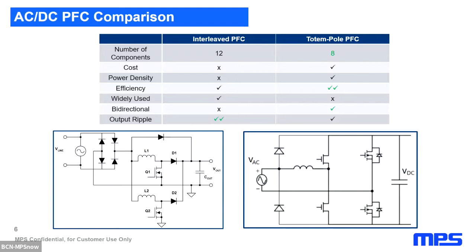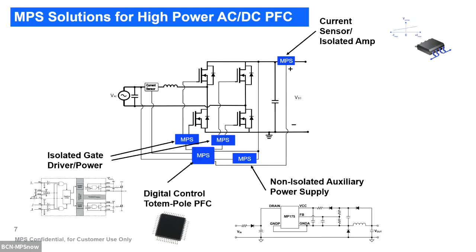The totem pole PFC has an inherent DC-AC behavior, so without changing the topology we can implement a bidirectional option. Interleaving PFC, which is mainly two boost converters in an interleaving configuration, has lower ripple because the two current sources are in parallel — with the same capacitor we get less ripple. This is our solution, our reference design, and we have a broad set of DC-DC solutions inside this application.